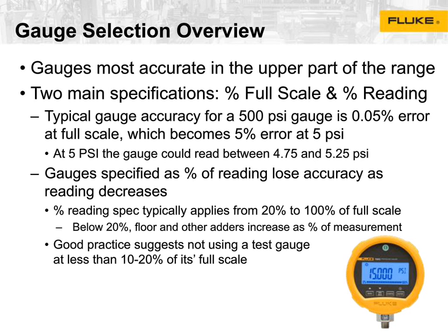And if you have a wide variety of working loads, let's say you spend some of your time at 1500 psi and some of your time at 300 psi, you might want to buy a 500 psi gauge and a 2000 psi gauge to cover the loads. Because the lower the pressure is as a percentage of the full scale, the higher the error ends up being. I've got the example here on the page that shows how a 500 psi gauge gives a fairly substantial error at 5 psi. It actually will give you 5% error, even if it has a very accurate 0.05% error spec.